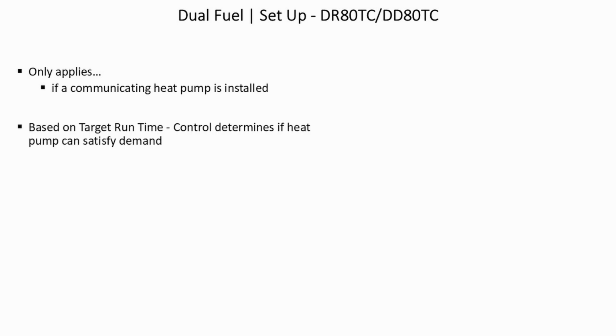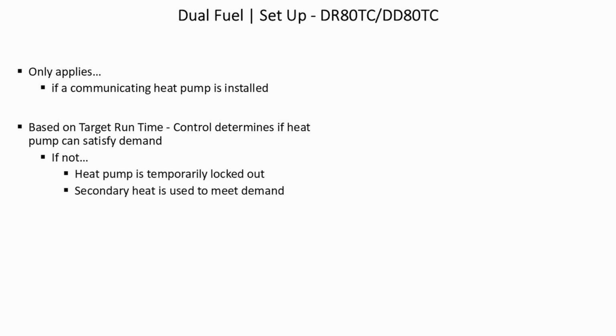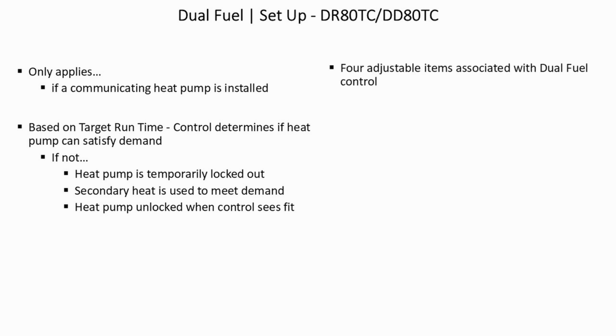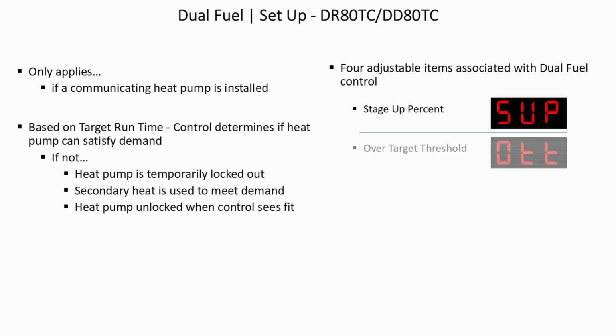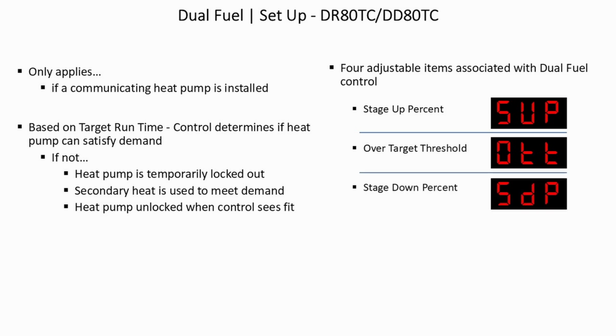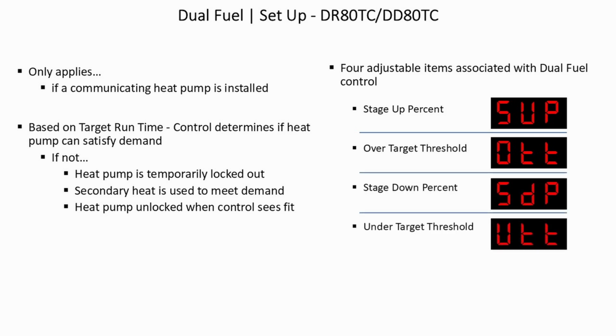Dual fuel setup. This only applies if a communicating heat pump is installed. Based on target run time, the control determines if the heat pump can satisfy the demand. If not, the heat pump is temporarily locked out. The secondary heat is used to meet the demand, and the heat pump is unlocked when the control sees fit. 4 adjustable items associated with dual fuel control are stage up percentage, over target threshold, stage down percentage, under target threshold.